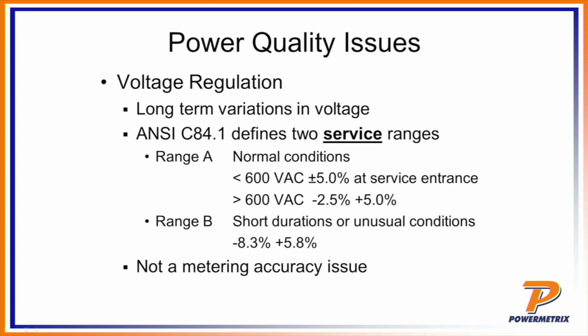For greater than 600 volts, you're giving a plus 5% on the high end and minus 2.5% on the low end, so it's a little bit tighter just by the fact that the equipment probably doesn't want to deal with a lot less voltage than that. Range B is defined as a short duration or unusual condition. So that would be more like the sag or swell or transient conditions that we mentioned earlier.